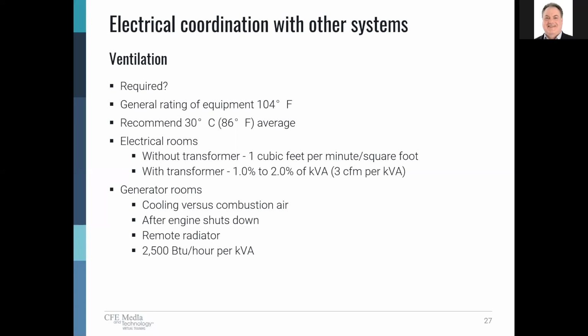If you have transformers, you're going to use 1 to 2% of the kVA, or 3 CFM per kVA, for ventilation. Again, check with your vendors for equipment. The mechanical engineers, if they're experienced, may also have their own guidelines that they've been using.